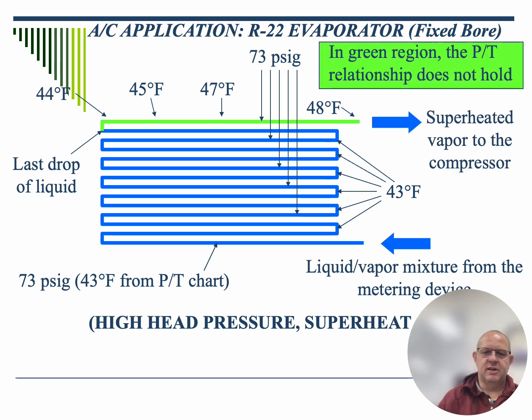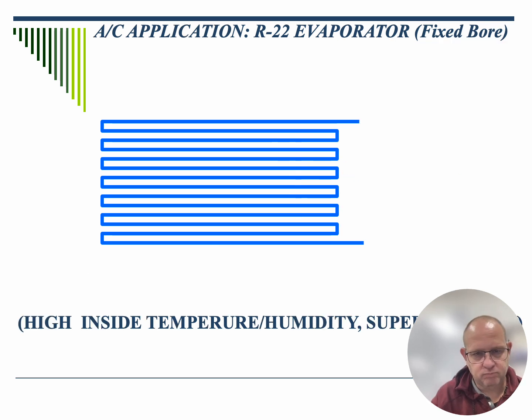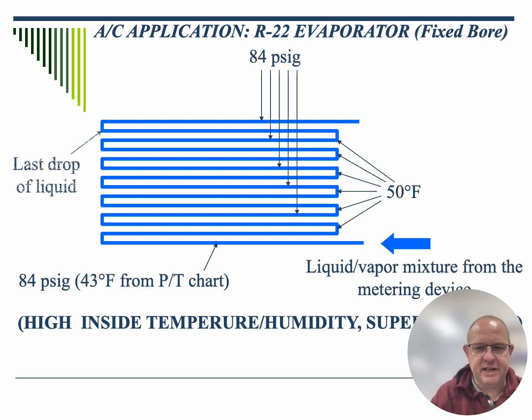So this system has a condensing temperature of around 135 degrees, which means the outdoor temperature is around 105 degrees. So your superheat value will drop if that is the case on that system. On this particular unit, what we've done is increase the temperature and the humidity within the system. We're dealing with a superheat that is well up to 20 degrees.